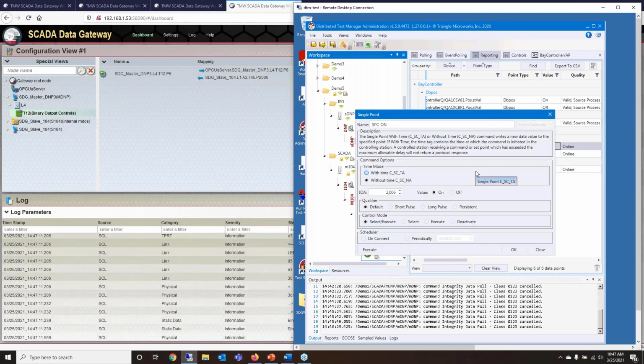As mentioned, we have the protection of select-before-operate, or select-before-execute. But if this wasn't something so risky, say not a breaker position, we could just do the direct operate or direct execute. Here we have it configured to do select-before-operate, and we've got the index we're working on, which is 2006.